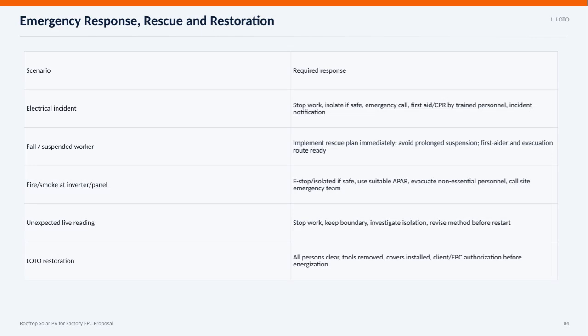Here, we focus on emergency response, rescue, and restoration protocols specific to rooftop solar PV installations. Each scenario demands a precise and swift response to ensure safety and minimize damage. For an electrical incident, work must stop immediately, and if it's safe, isolate the source. Emergency calls should be made without delay, and first aid or CPR administered by trained personnel while notifying the relevant parties. In the case of a fall or a suspended worker, we must implement the rescue plan right away to avoid prolonged suspension, with a first aider and clear evacuation routes ready.